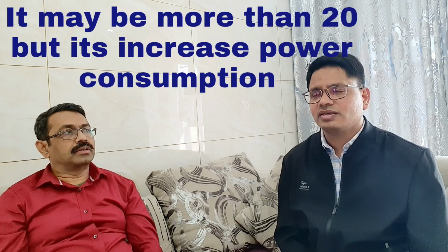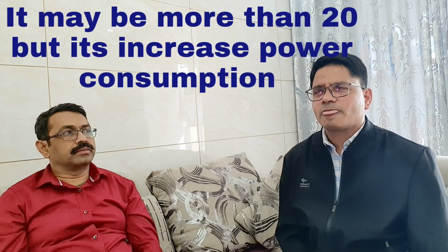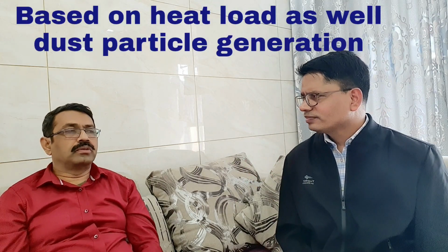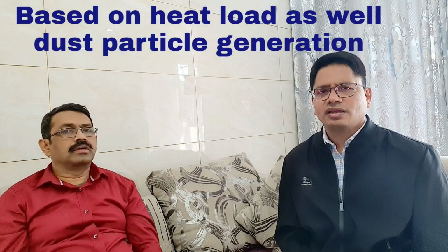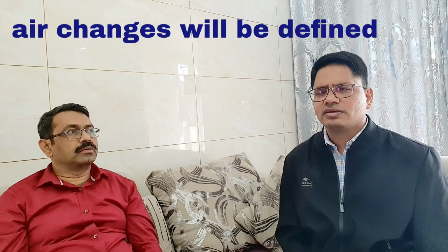That is an optimum design, like 6 to 20. So is there a specific area where 6 has to be done and a specific area where 20 should be there? Simple - if there is no dust, we can go with 6 air changes. If dust is more, we can go up to 20 air changes.